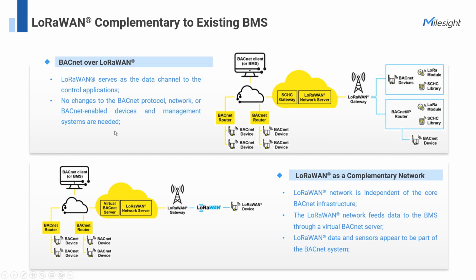The first approach is BACnet over LoRaWAN, where LoRaWAN serves as the data channel to the control applications. It's very easy to implement, as there are no changes needed to the BACnet protocol or to the network and BACnet-enabled devices. The second approach is to deploy LoRaWAN as a complementary network, focusing on integration with the BMS system.